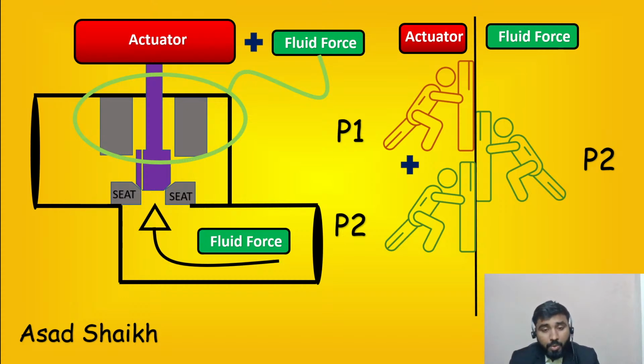A lot of times what happens as engineers is, you give a requisition to a particular vendor, and the vendor definitely has to save cost. He would not see any clause in your data sheet saying that there are going to be solid particles. You missed mentioning that clause, and he gives you a balanced design. Now when it gets to the plant, that hole will get stuck and your valve will not function properly. It will not close and you will have an extremely high leakage rate.